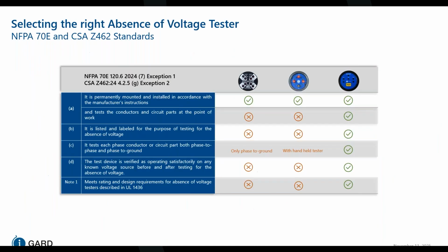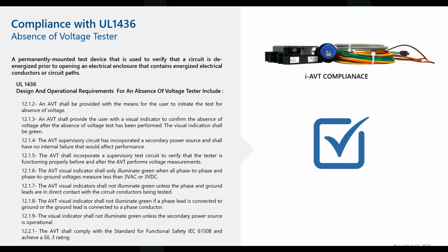Not all devices meet NFPA 70E and CSA Z462 standards for verifying absence of voltage. To comply, the tester must be permanently mounted, test conductors at the actual point of work, and be listed for this purpose. It should check all phase-to-phase and phase-to-ground connections and verify its own operation using a known voltage source before and after testing. Finally, it must meet all UL 1436 design requirements. Many indicators and portals fail these criteria. They only show voltage presence and require a handheld tester for confirmation. A true absence of voltage tester meets all the requirements, ensuring compliance and maximum safety. Compliance with UL 1436 ensures maximum electrical safety.